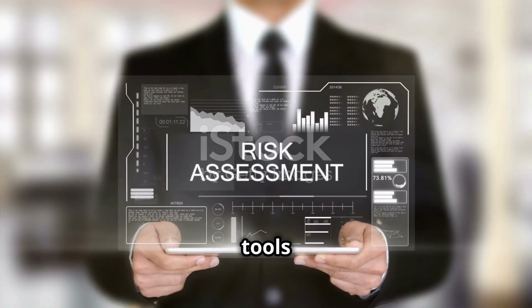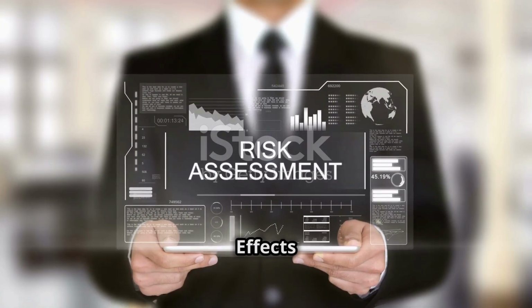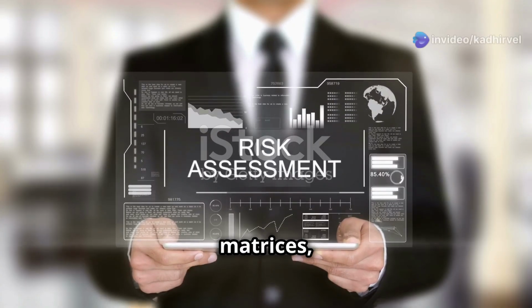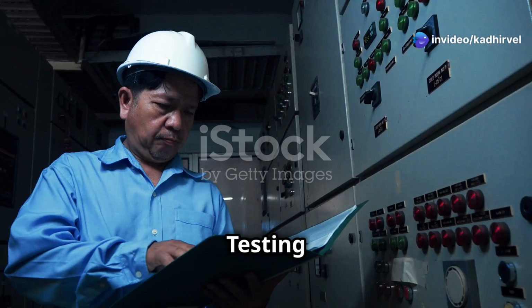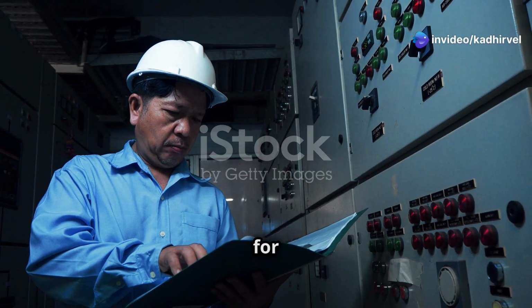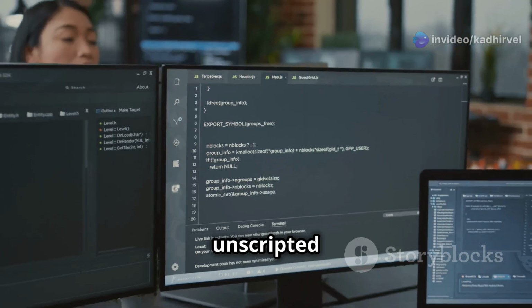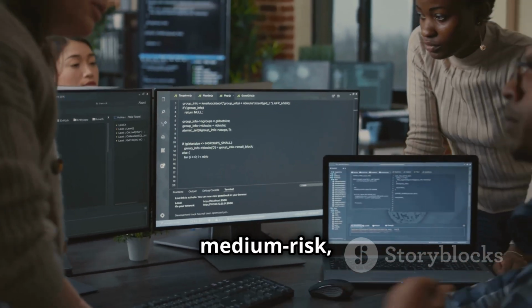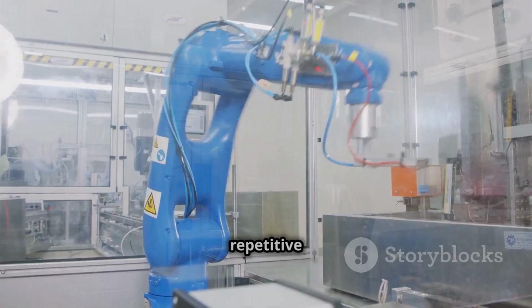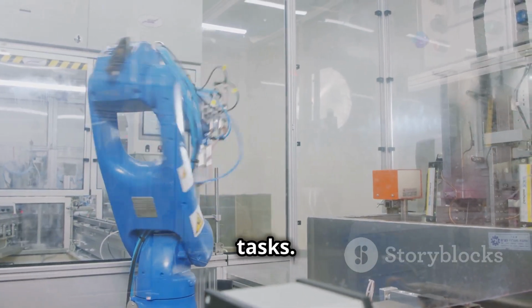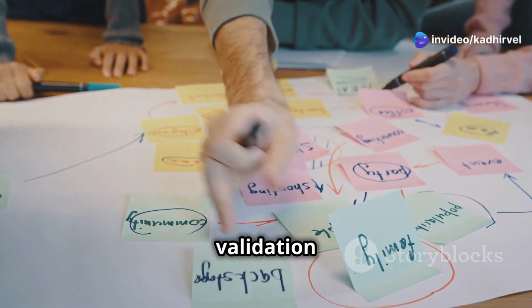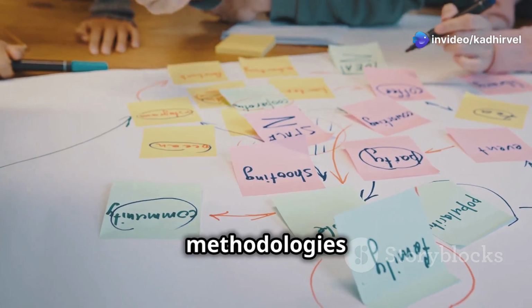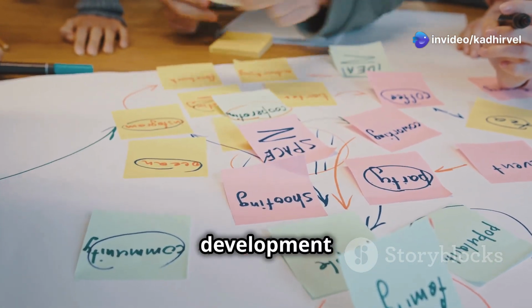Risk assessment tools: FMEA, or failure mode and effects analysis, risk matrices and risk registers. Testing methods: scripted testing for high-risk functions, unscripted or ad hoc testing for low to medium risk, and automated testing for repetitive or critical tasks. Agile validation: CSA supports agile methodologies for iterative development and testing.